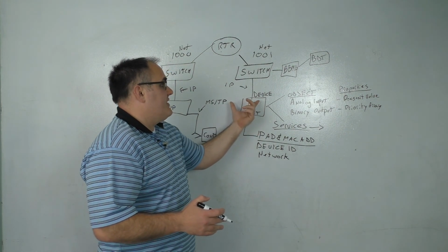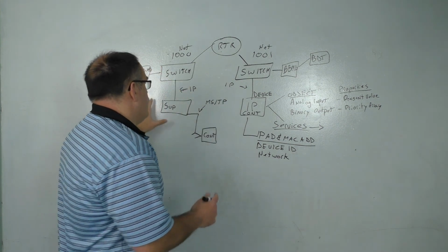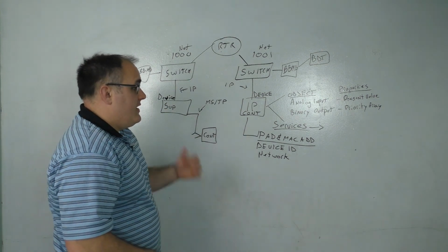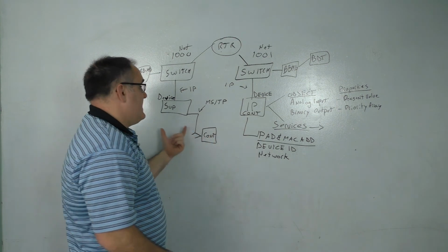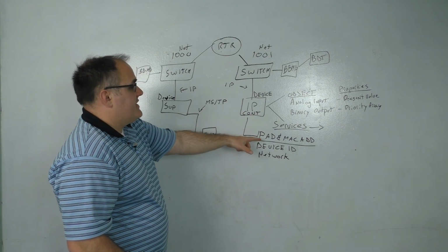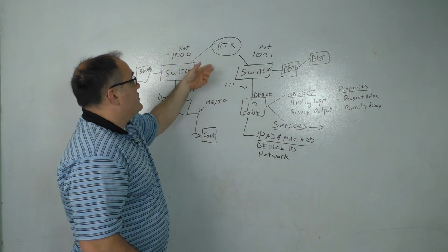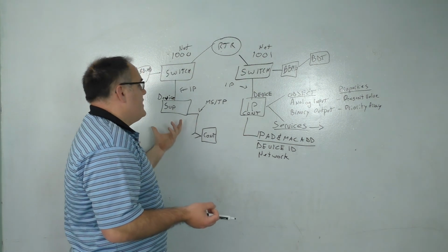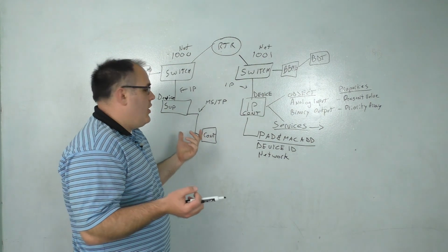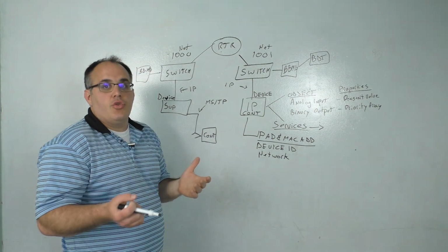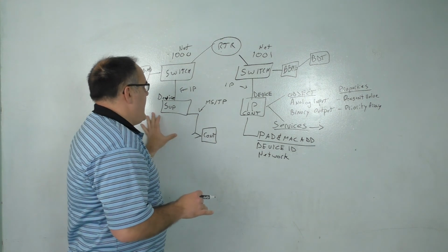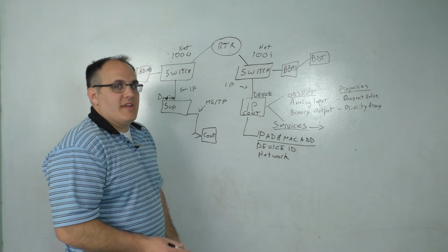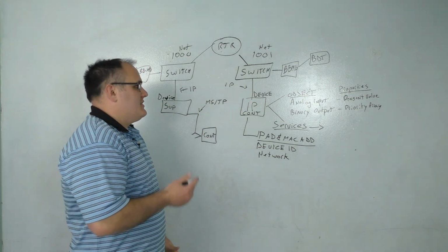So what will happen, for example, is this device wants to communicate to this device over here. This is a supervisory device. It's going to need to know the IP address and MAC address and device ID. And once it knows the IP address and knows it's not on that network, it's going to communicate to the BBMD, which will do a Who-Is service message. That Who-Is service message discovers that device if it doesn't already know it, creates a connection across the BACnet virtual link. I know I'm throwing a ton at you right here. And basically they communicate to one another. That's a very high-level overview of BACnet IP communications, but this is a free video, so hey.